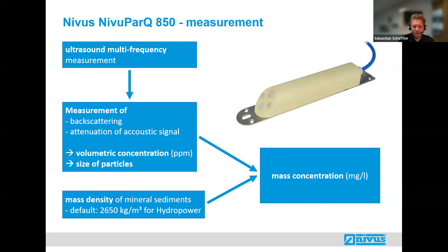And with this, until now, we are able to measure the concentration in the measurement range from 10 to 6,000 milligrams per liter, and this without any calibration. In 2 or 3 weeks, we will launch a new firmware. With this new firmware, we will be able to measure within a measurement range from 10 to 50,000 milligrams per liter or even more.